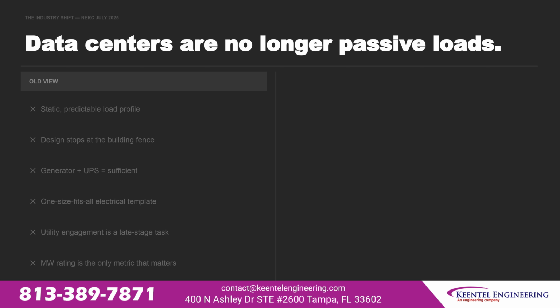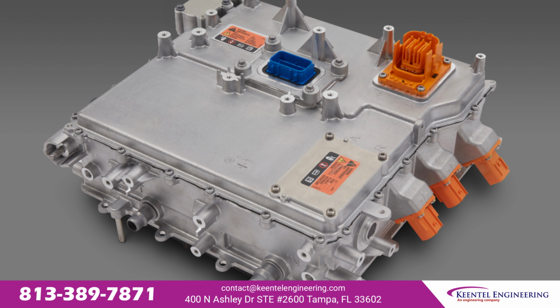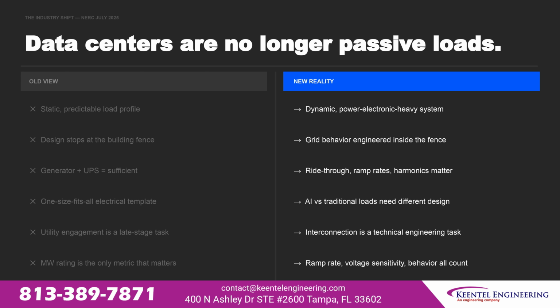NERC's July 2025 paper marks a formal shift in how data centers are classified. The old view: static predictable load, design stops at the building fence, generator plus UPS equals sufficient, one-size-fits-all templates, utility engagement is a late-stage task, and megawatt rating is the only metric that matters. The new reality: dynamic, power-electronic-heavy systems, grid behavior engineered inside the fence, where ride-through, ramp rates, and harmonics all matter. AI and traditional loads need different designs. Interconnection is a technical engineering task, and ramp rate, voltage sensitivity, and operating behavior all count. That shift from old to new is the entire premise of this presentation.